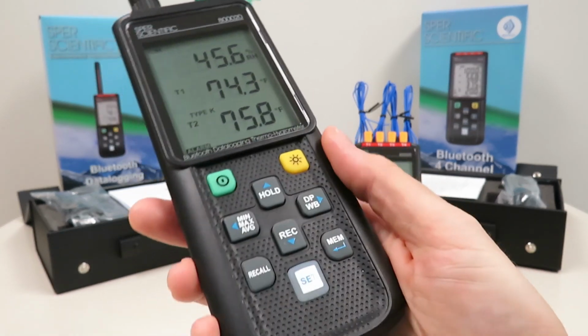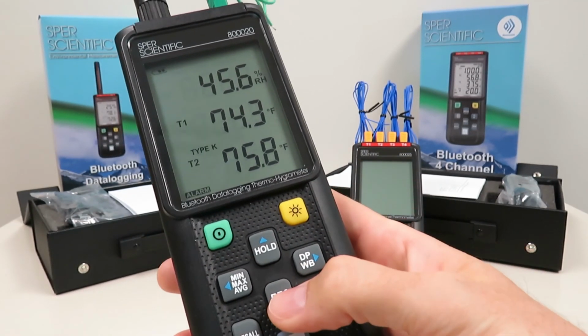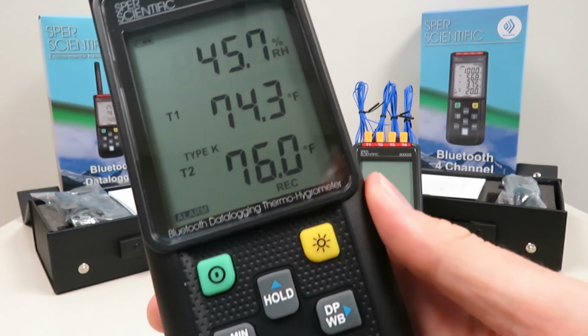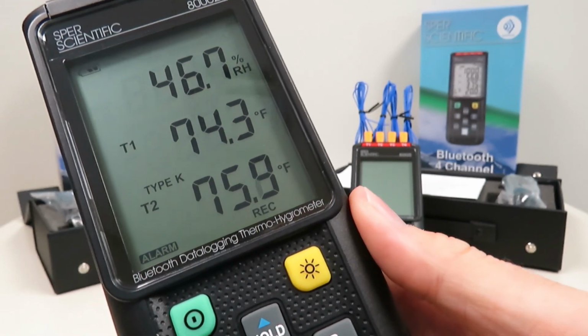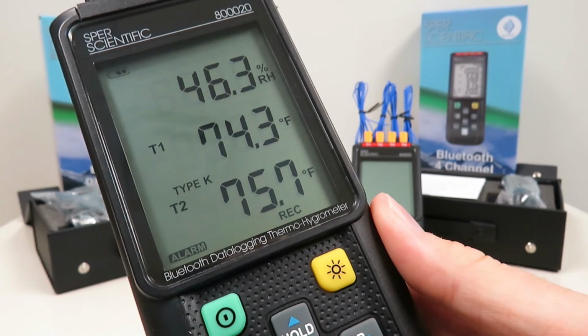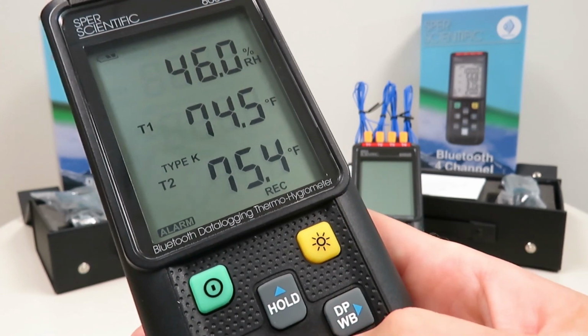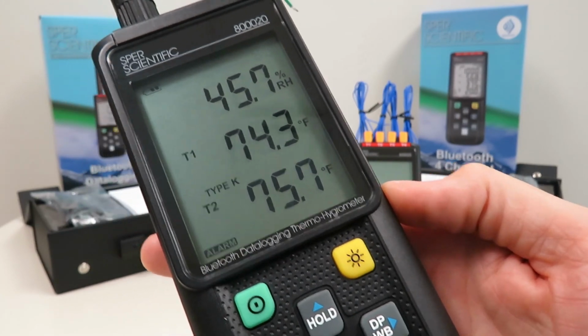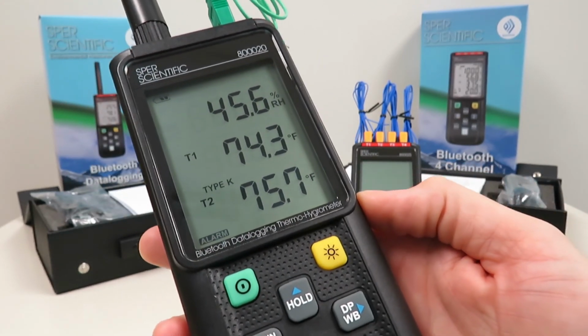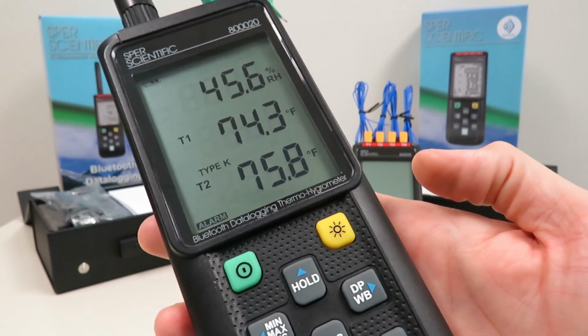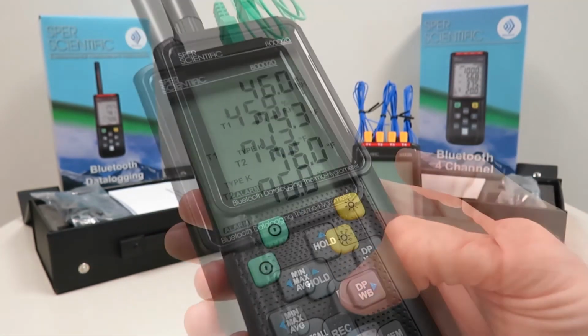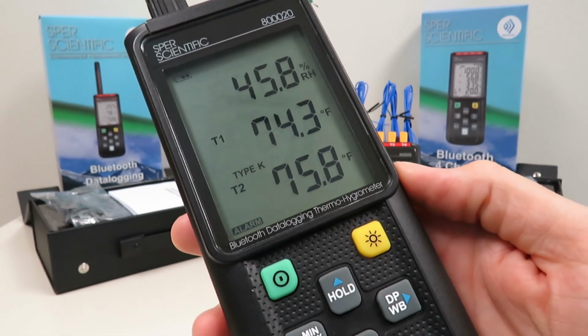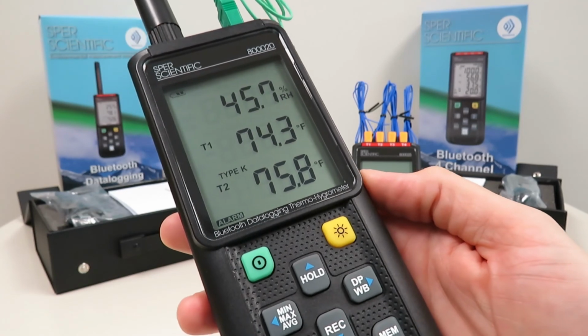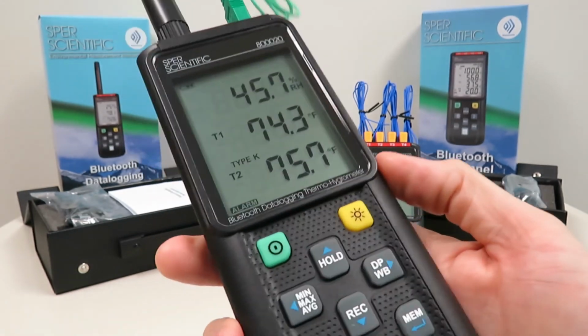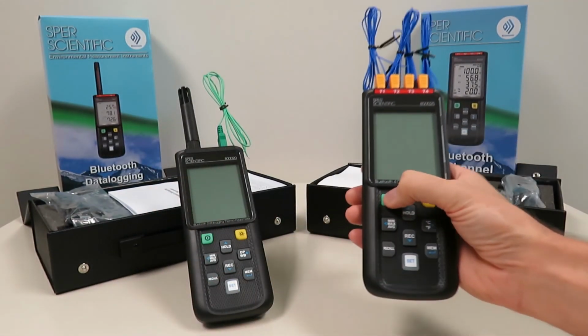Another feature it has is it will let you record data at whatever interval you set it at. I set it for 1 second, so every second it's taking a reading. Just press record again and it stops taking your data readings. And this can be downloaded later via Bluetooth or also connected with a cable if you don't have Bluetooth connection. When you record, it can store up to 32,000 data points on each channel. So it's really helpful.